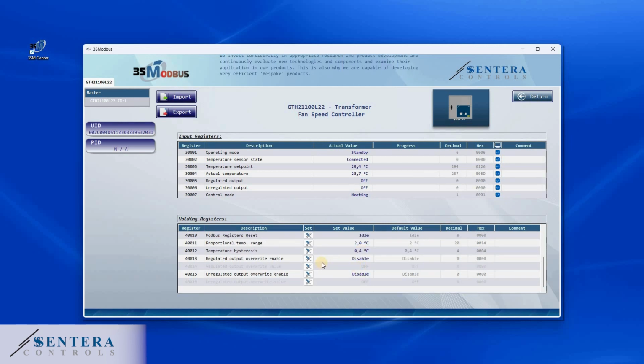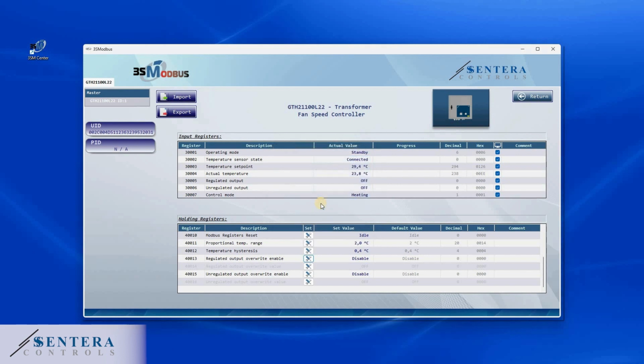That's what we chose. The holding registers are used for setting the device. I will show you how to change the output step of the controller. For the purpose, I first need to override the output, meaning I will replace the step set manually using the knob by the Modbus holding register setting, which will happen via holding register 13. So here I choose Enable.